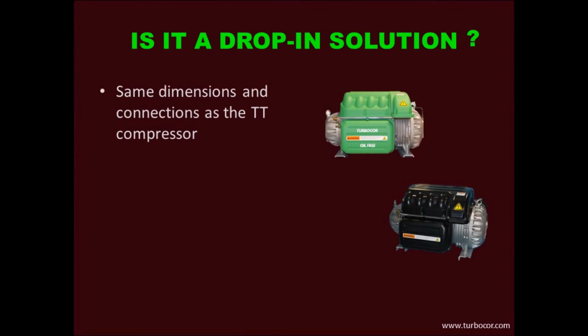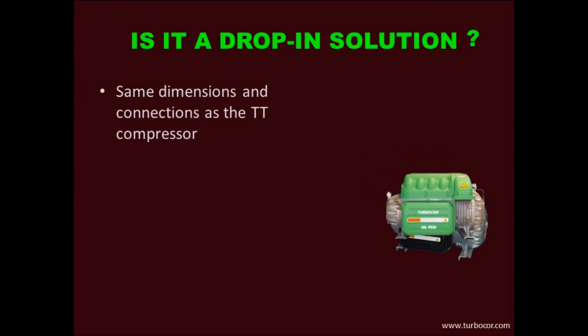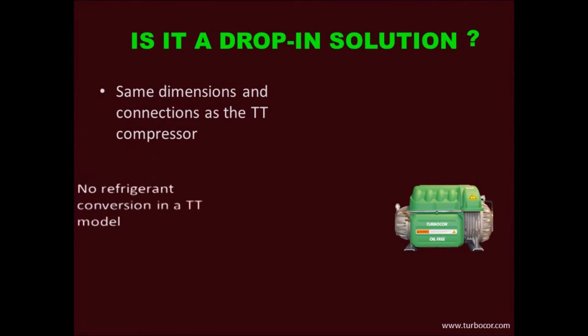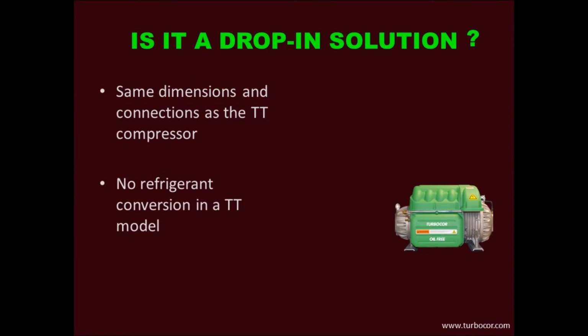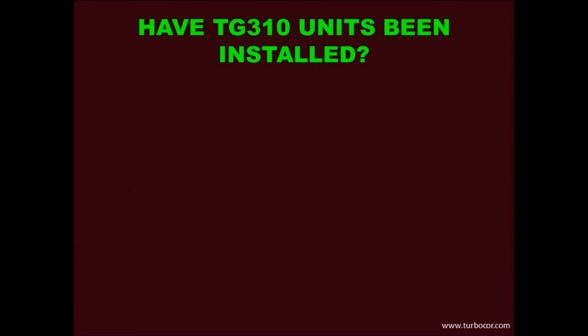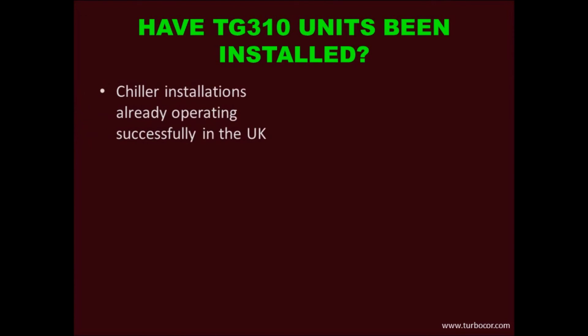Is it a drop-in solution? The TG310 compressor has exactly the same dimensions and connections as the TT. It can replace an existing TT compressor. However, it is not possible to field convert an existing TT compressor to a TG compressor. Have TG310 units already been installed in the field? Yes, there are OEM chiller installations already operating successfully in the UK.